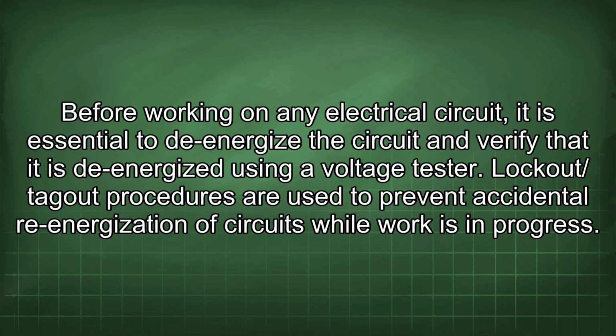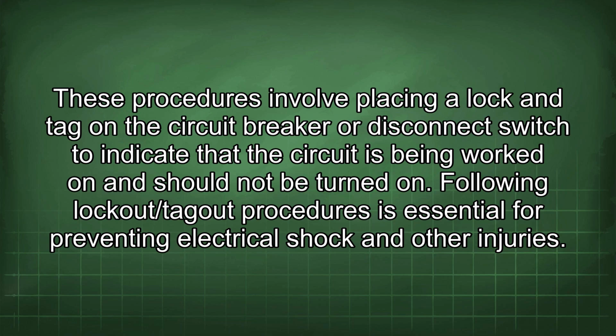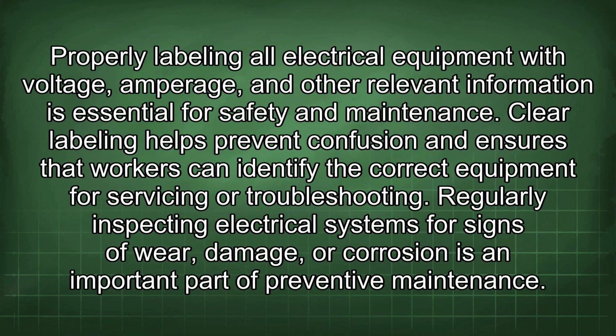Before working on any electrical circuit, it is essential to de-energize the circuit and verify that it is de-energized using a voltage tester. Lockout/tagout procedures are used to prevent accidental re-energization of circuits while work is in progress. These procedures involve placing a lock and tag on the circuit breaker or disconnect switch to indicate that the circuit is being worked on and should not be turned on. Following lockout/tagout procedures is essential for preventing electrical shock and other injuries. Properly labeling all electrical equipment with voltage, amperage, and other relevant information is essential for safety and maintenance.